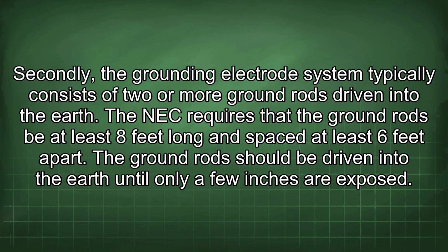Secondly, the grounding electrode system typically consists of 2 or more ground rods driven into the earth. The NEC requires that the ground rods be at least 8 feet long and spaced at least 6 feet apart. The ground rods should be driven into the earth until only a few inches are exposed.